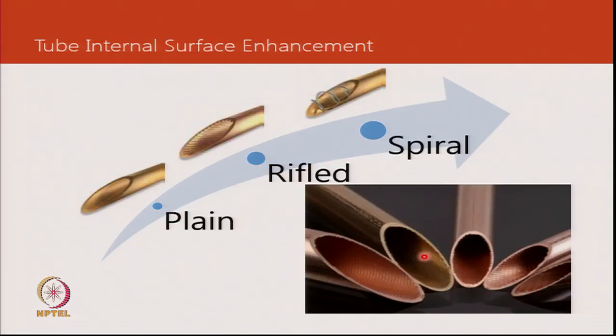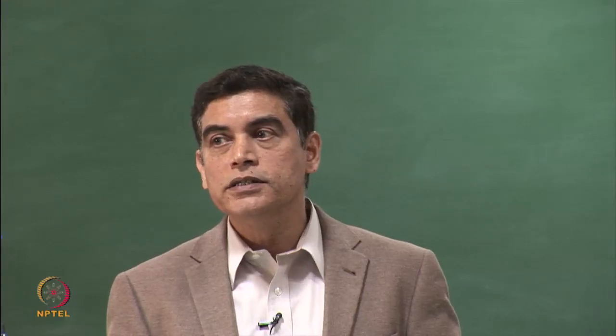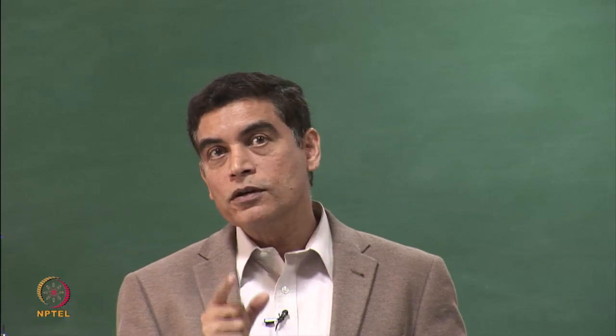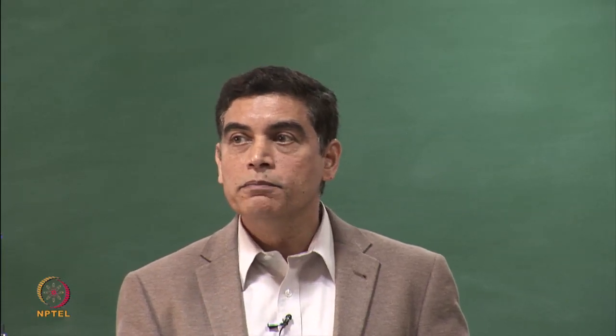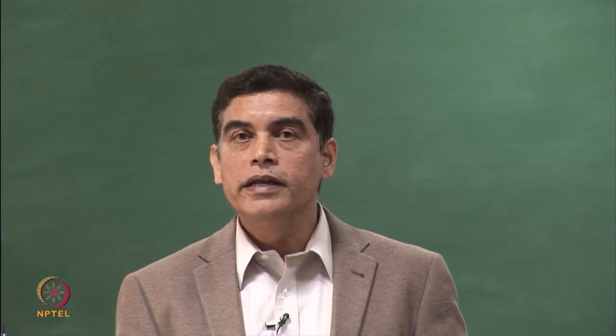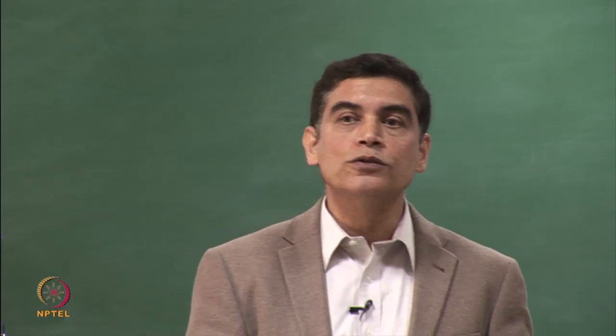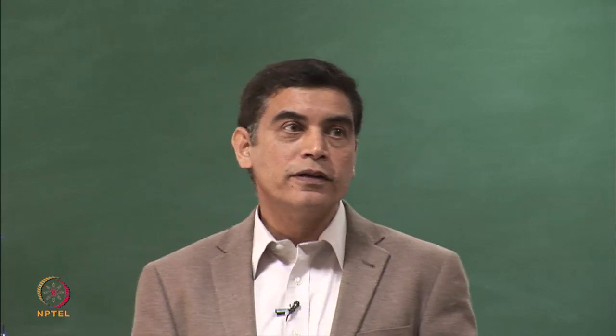And then there could be further turbulence generated by inserting something like a spiral wire inside the tube. So this spring kind of arrangement further enhances the thing, and it is used in different designs differently, because if your intention is to enhance the heat transfer coefficient in a certain area of the tube only, then because there is a cost and complexity associated with implementing such an enhancement, you would do it specifically for those tubes where you want to benefit from this.